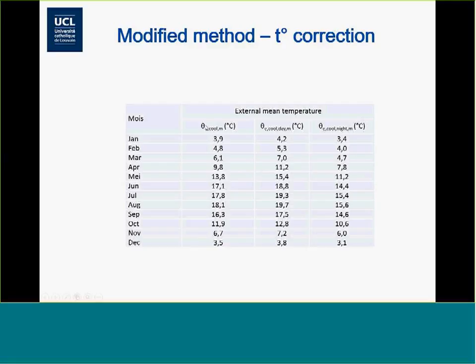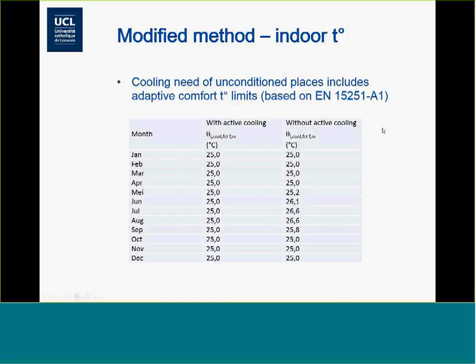So to go a little bit into numbers, you have in this table the mean monthly temperature, and so for example in July it's nearly 18 degrees. It will be turned into 19.3 degrees in days and 15.4 degrees in night. This is quite important to be able to consider nighttime ventilation, because you see the temperature difference between indoor and outdoor will shift from something which is like 25 minus 18, let's say 7 degrees, to something which is more close down, nearly 10 degrees. So it's 30% more impact for the nighttime ventilation than before, just by changing this hypothesis of outdoor temperature.